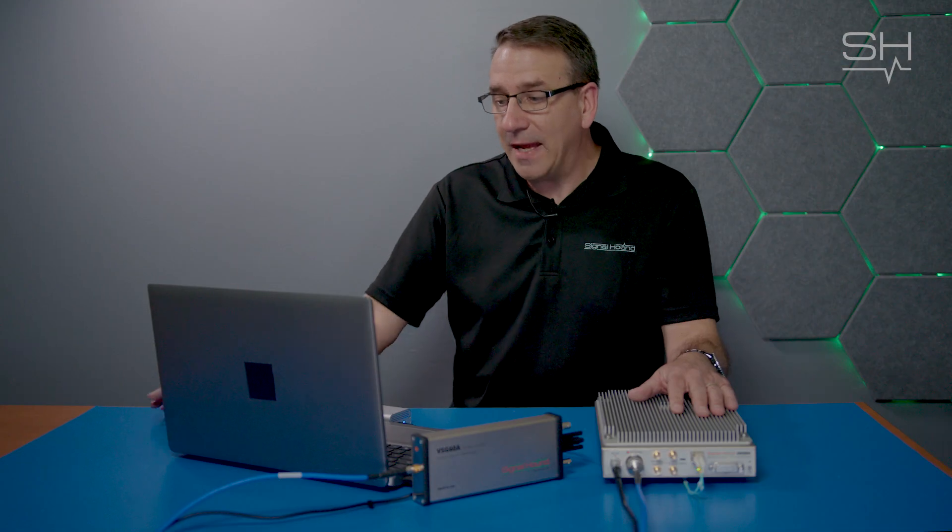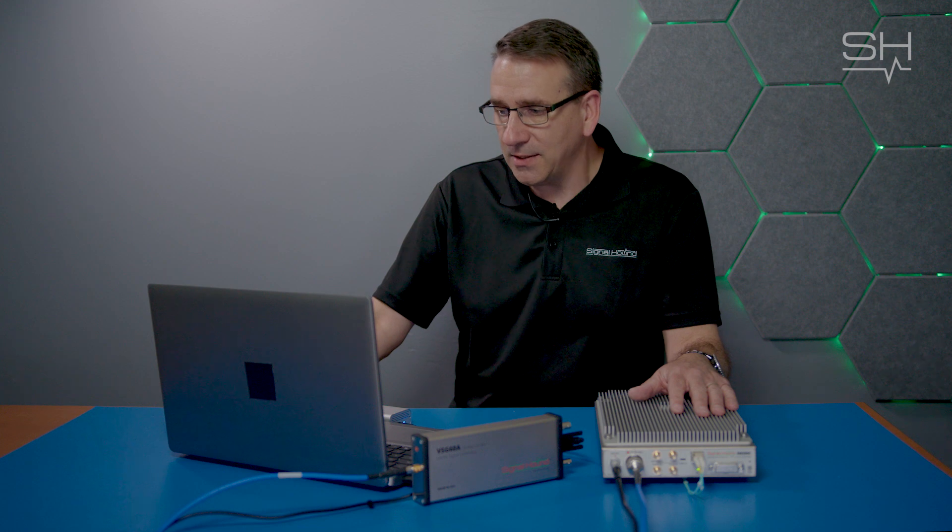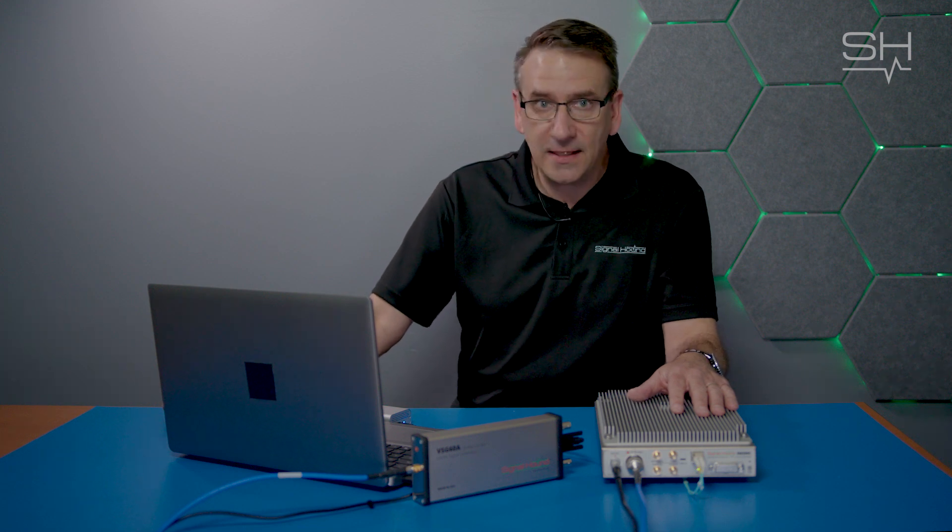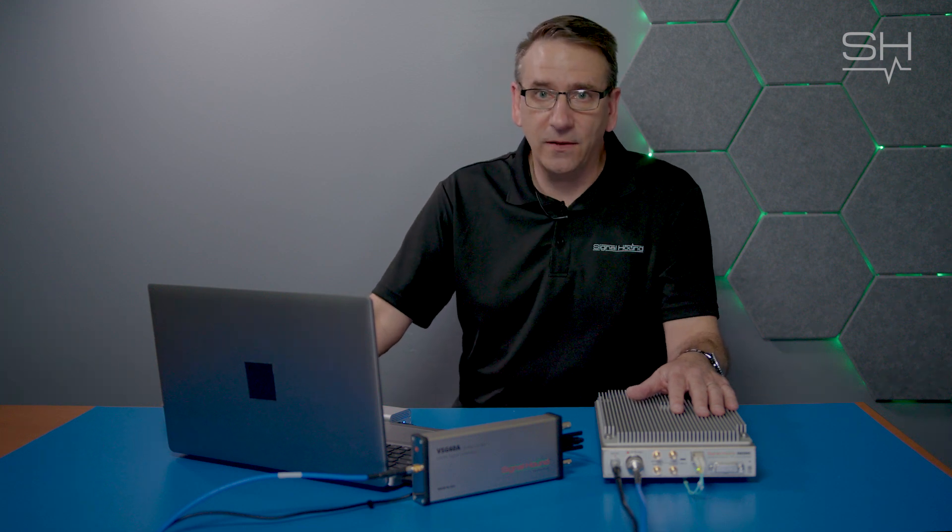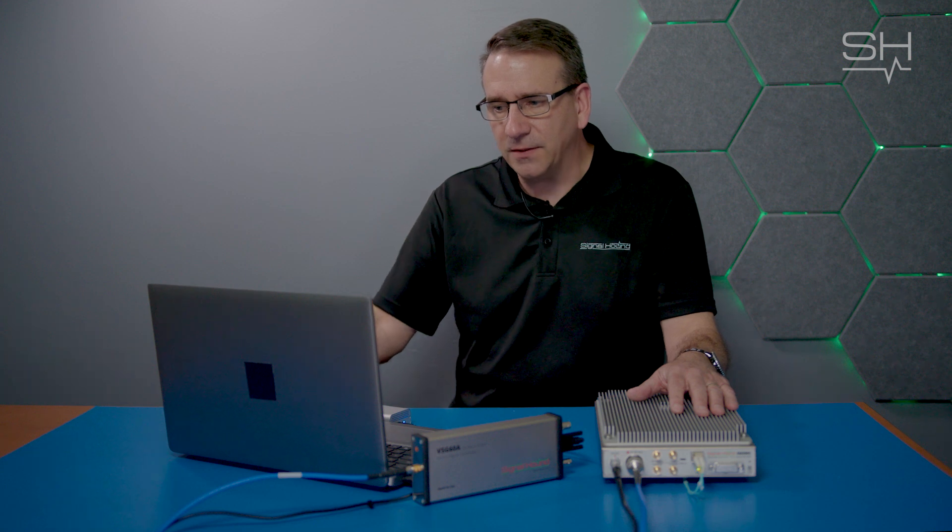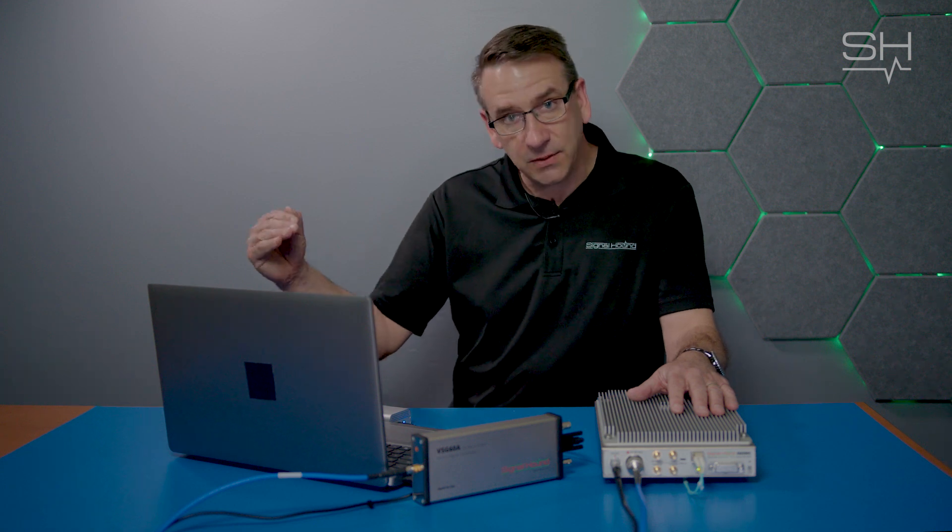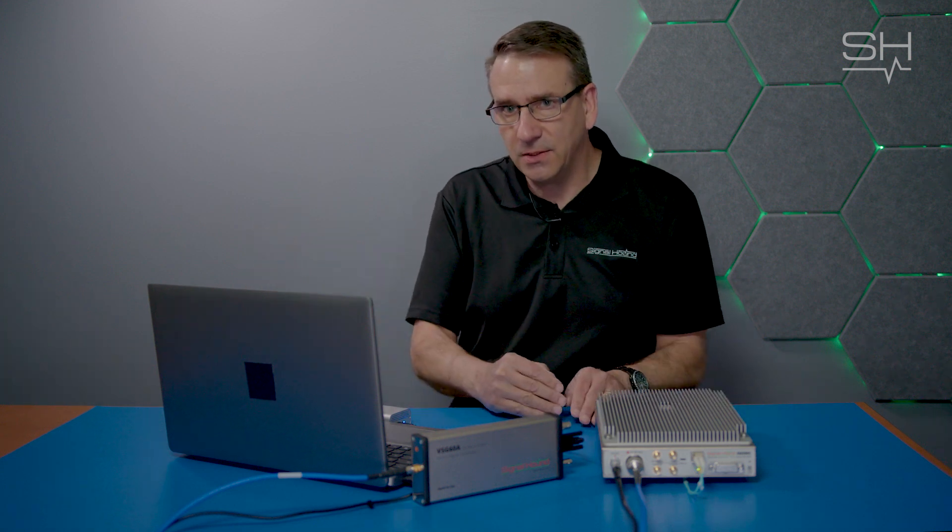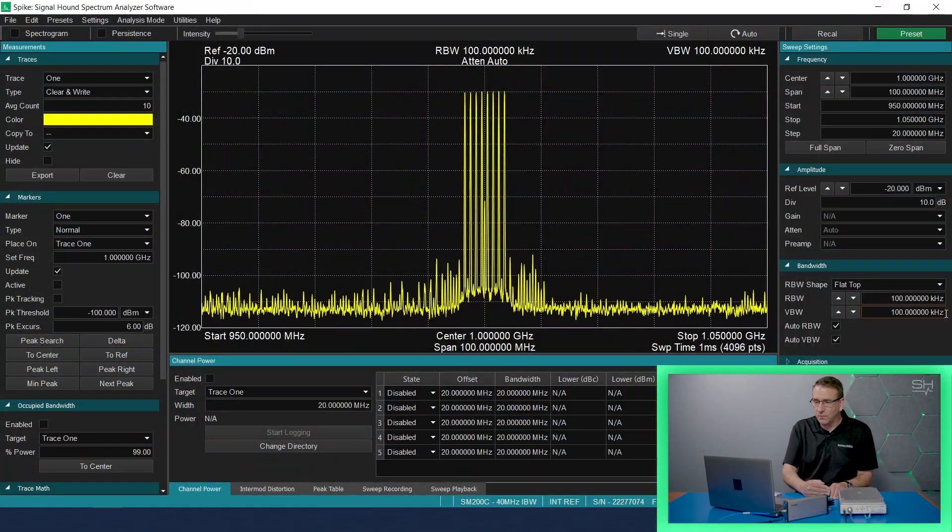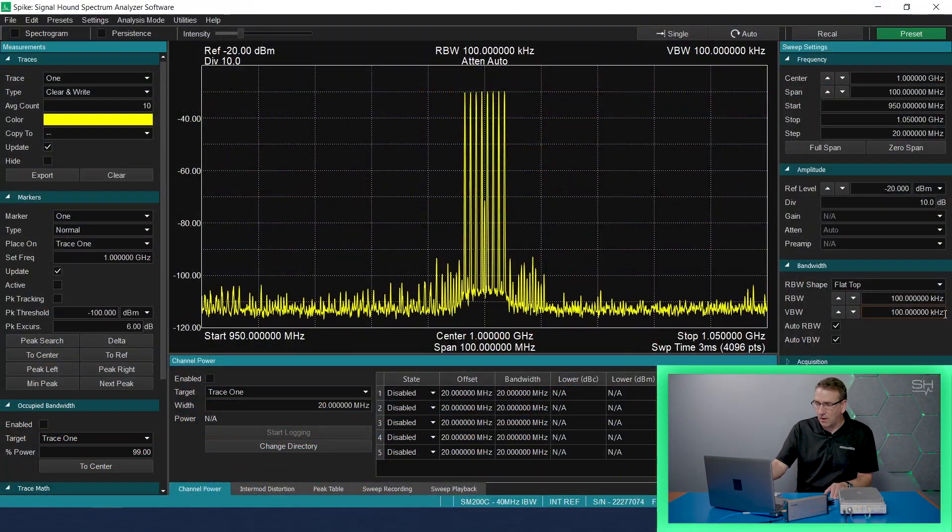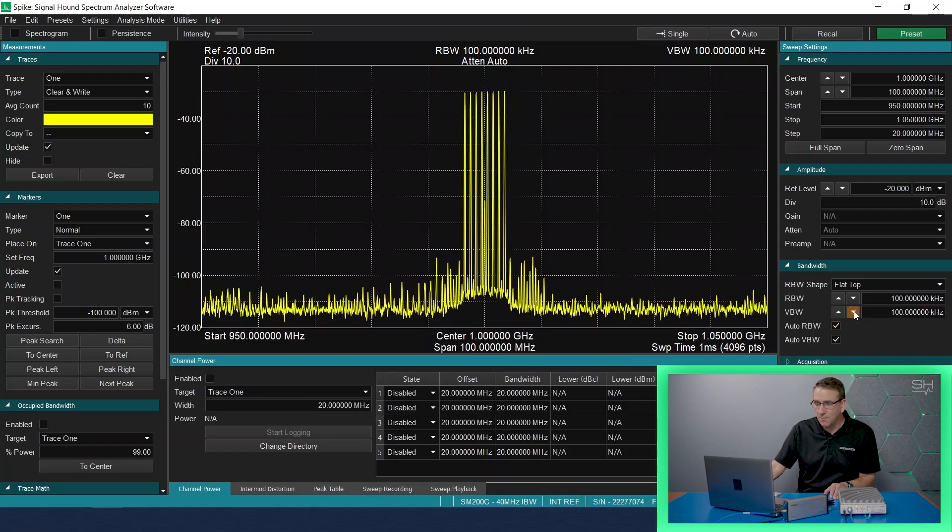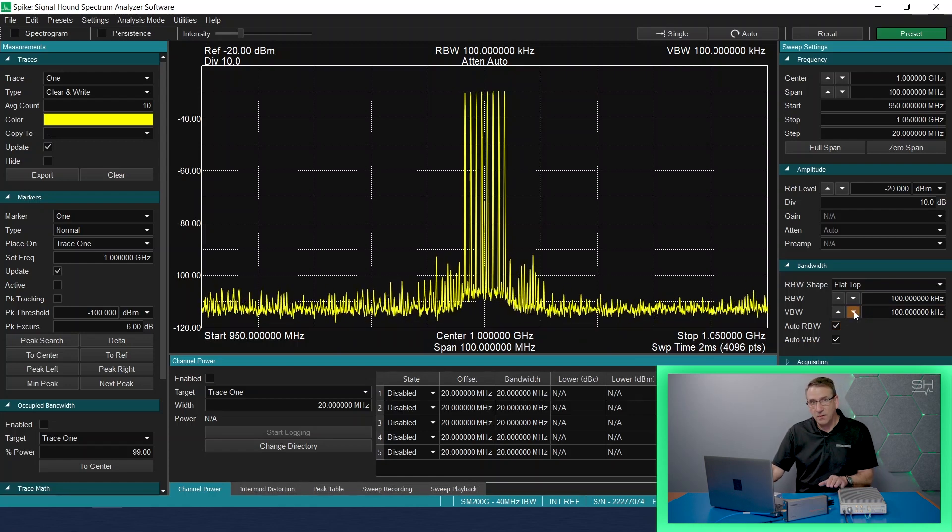There's another bandwidth filter that we can adjust in the bandwidth settings, and that's the video bandwidth filter. The video bandwidth filter is an additional filter that will filter on the amplitudes post the resolution bandwidth filter. Adjusting this video bandwidth filter will have an impact on sweep speeds. It will decrease the sweep speeds, but it can get rid of some of the noise.